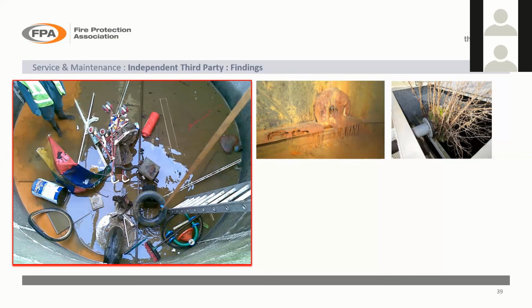To the left there, you can see somebody's dropped something that looks like a parasol. If that got dragged into the vortex inhibitor and then up the suction pipe into the pump, it would jam, or potentially jam, the impellers on the pump, damage the pump, maybe even wreck the pump completely. Certainly inhibit, or perhaps even prevent completely, the water from that tank going into your system and putting a fire out. So it could be what's in that tank there.